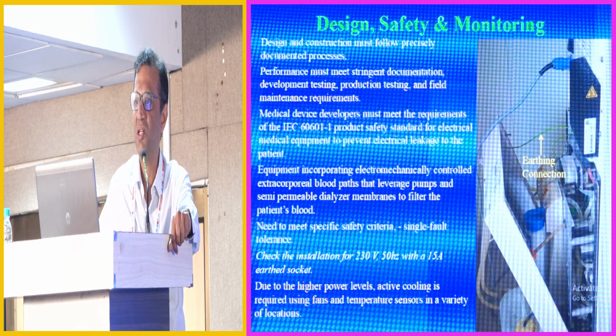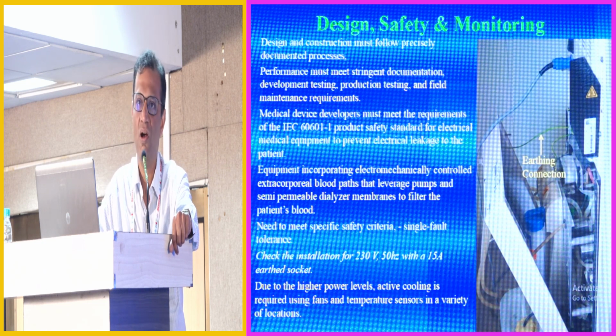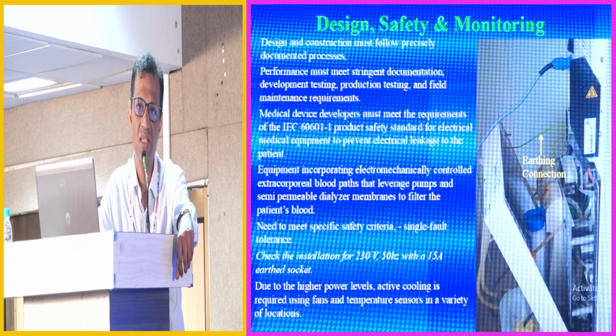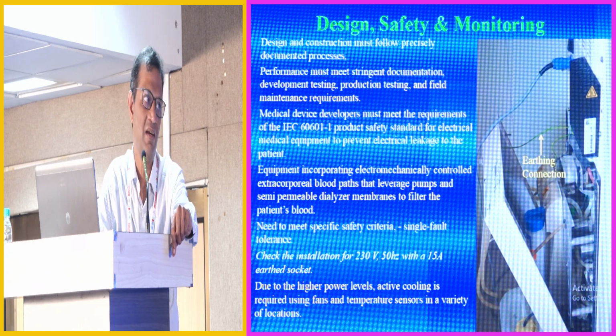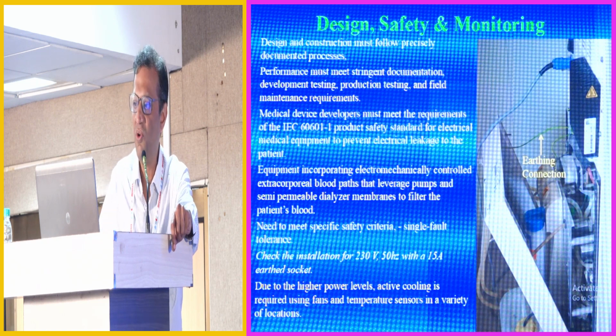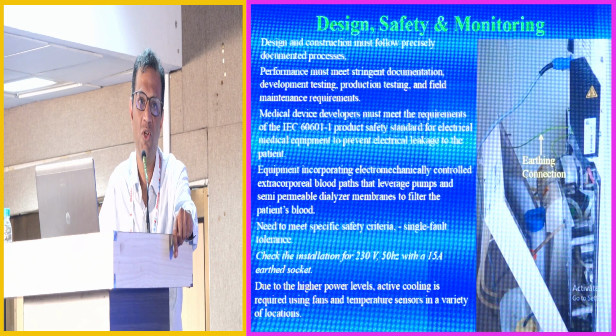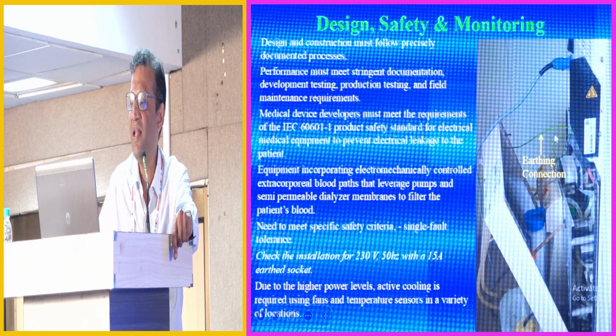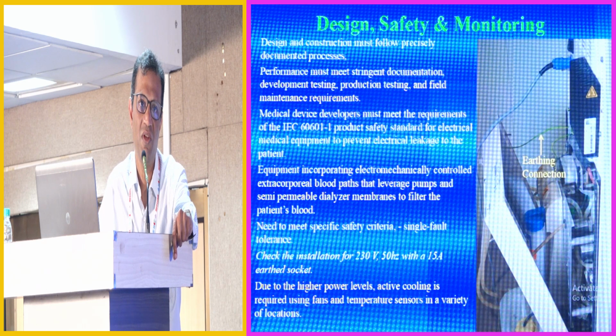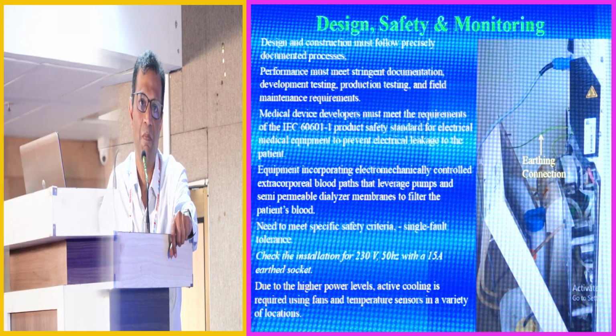So if you were to look at a machine, ISO calls a dialysis machine a class 1 device. That means that at no stage should the body of the machine conduct an electric current, because the blood lines could take that electric current directly to the patient. So it does this with the help of this earthing connection over here. So if you open your machine, you will find this green and yellow wire at the back, which is connected to the body of the machine and which connects to the earth socket of your mains, which means that a dialysis machine must always be plugged into an earthed supply.